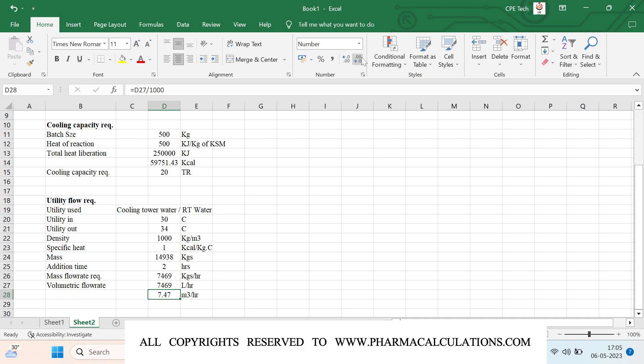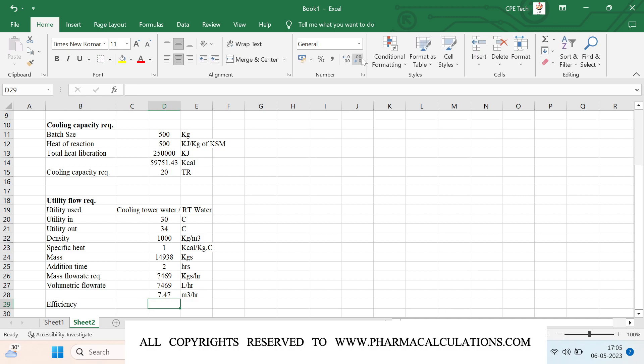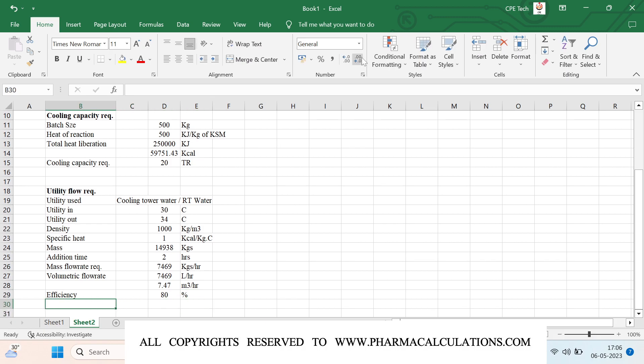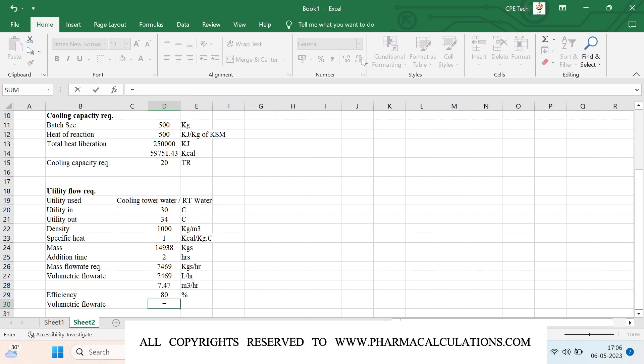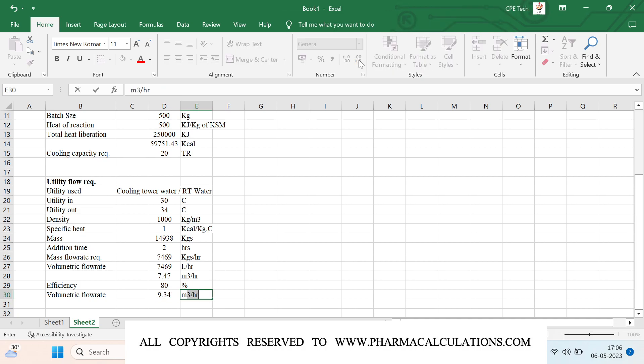We also need to account for efficiency. Assuming an efficiency of approximately 80 percent, the actual volumetric flow rate equals the theoretical volumetric flow rate divided by the efficiency. This gives approximately 9.34 meter cube per hour, which is the actual utility flow required.